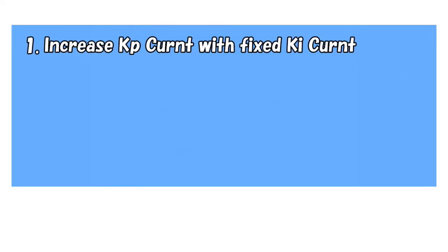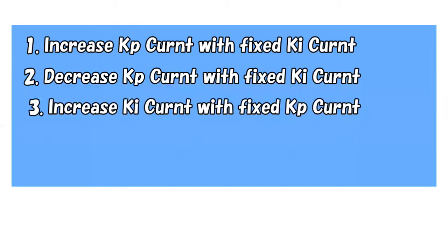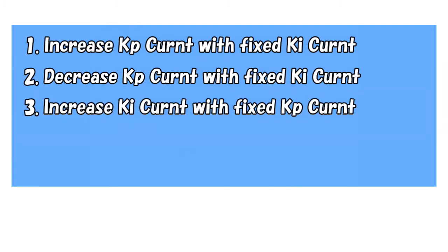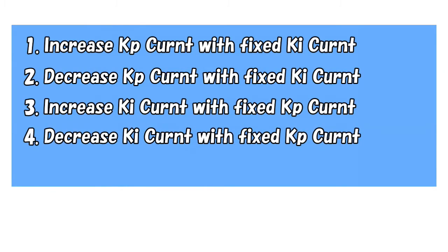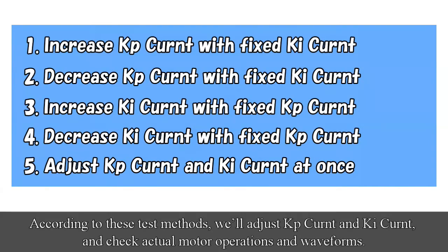Increase Kp current with fixed Ki current. Decrease Kp current with fixed Ki current. Increase Ki current with fixed Kp current. Decrease Ki current with fixed Kp current. Adjust Kp current and Ki current at once. According to these test methods, we'll adjust Kp current and Ki current, and check actual motor operations and waveforms.